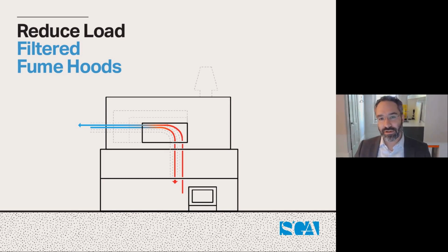And then you can take the air from the lab back out through the air handler, and do heat recovery on the way out. So all the energy you put into heating the air on its way in, you can take that energy back as you pass air back out to the outside. The efficiency for a heat exchanger can be in the upper 90% range. So you've taken your 1 watt of electricity, made 5 or 6 watts of heat, and when you send it back out through the air handler, you get to keep 4.5 watts. You're really getting quite a lot of mileage out of that 1 watt if you can get it back out through a heat recovery system.